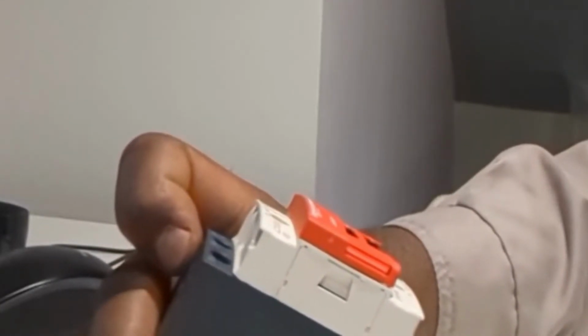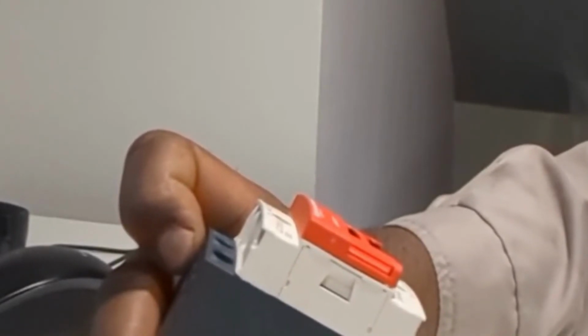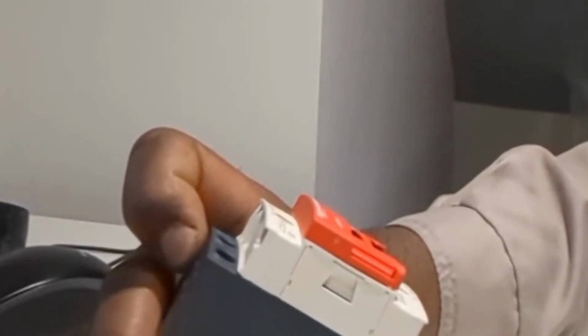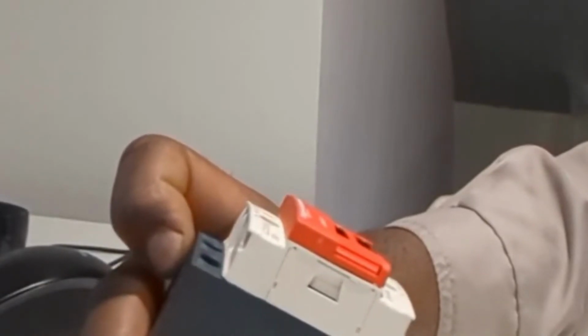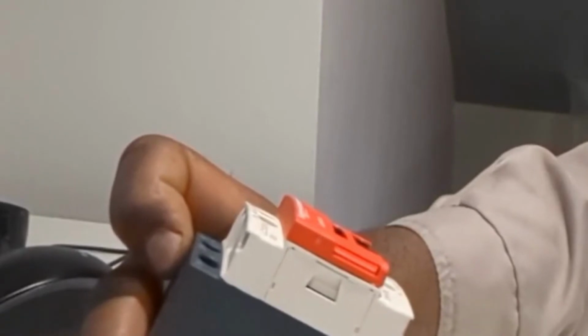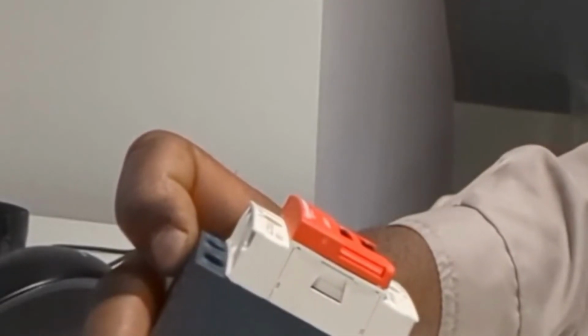So what you do in this kind of situation, if you want to pass single phase electricity, you can decide to loop it from L1 into L2 and L3. And if you've got three phase, you can let it pass through L1, L2, and L3 respectively. And when the contactor is energized through the coil, it passes electricity as an output at T1, T2, and T3. And with this, we're still going to be talking some other time more on contactors.